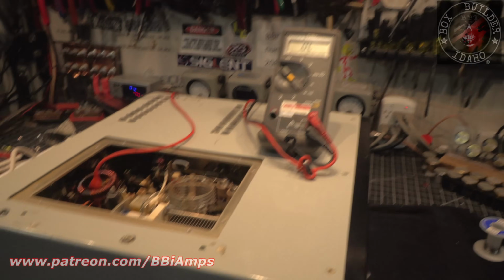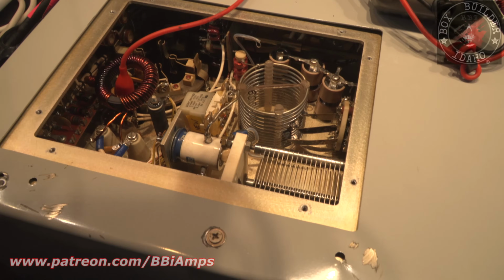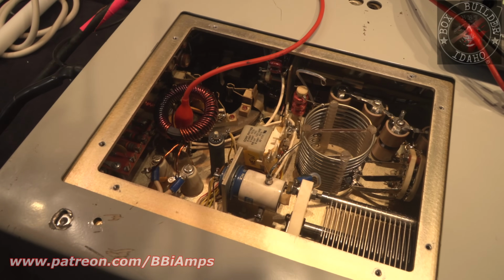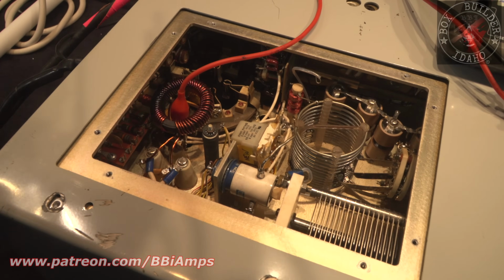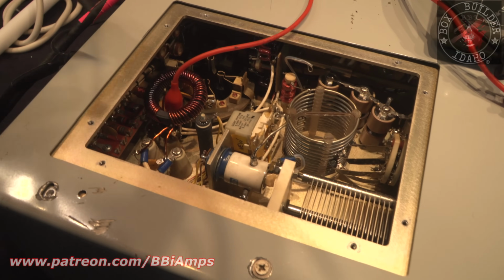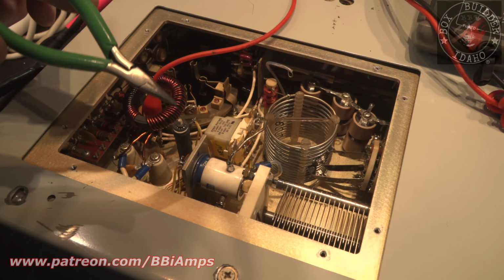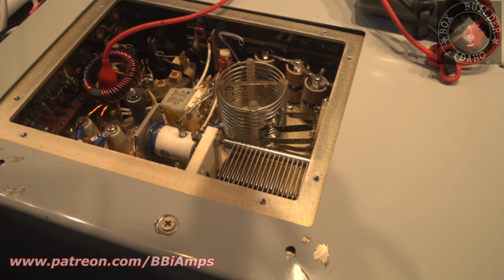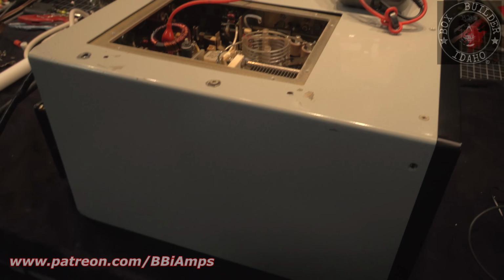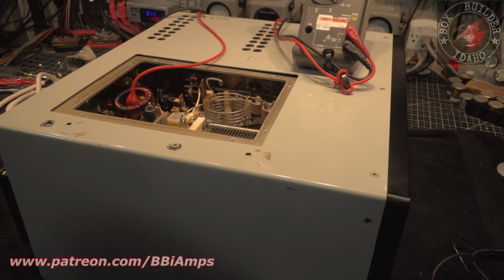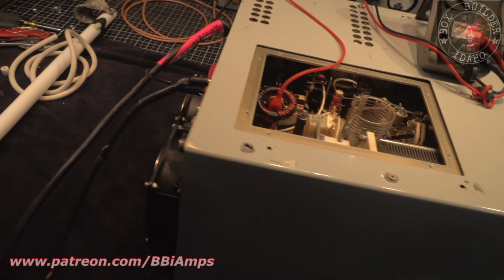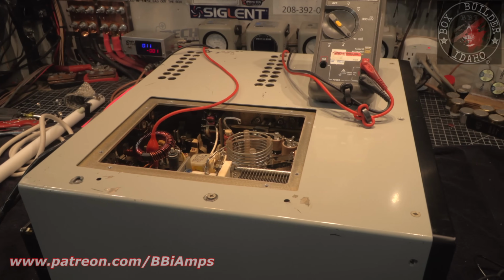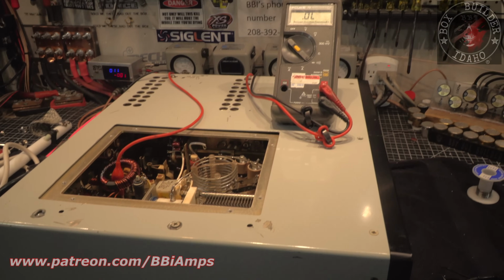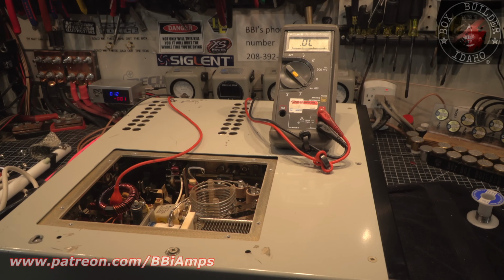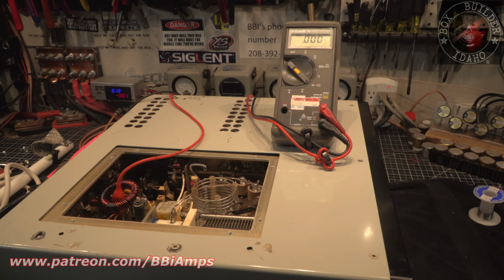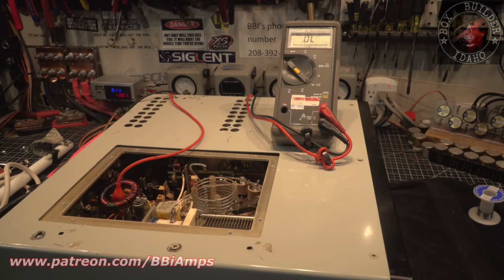So down in here, we have this little disc capacitor that you can almost barely see. It's sitting right next to where the probe is hooked up. And one of these white wires is the coax that comes around and goes to the relay. From the relay, it goes to the coax connector here on the back. And we've got the volt ohm meter hooked up to the coax connector on the back. And we'll know as soon as we step on the pedal, we should have a nice irritating screech. Yep, okay, so that tells us that the RF is making it into the tube.